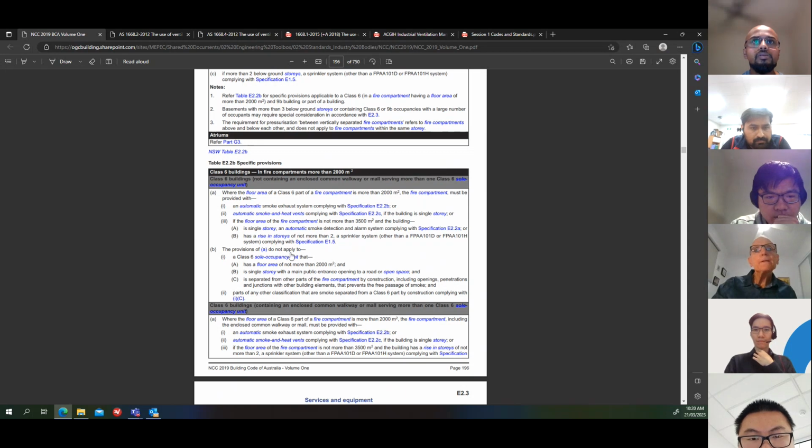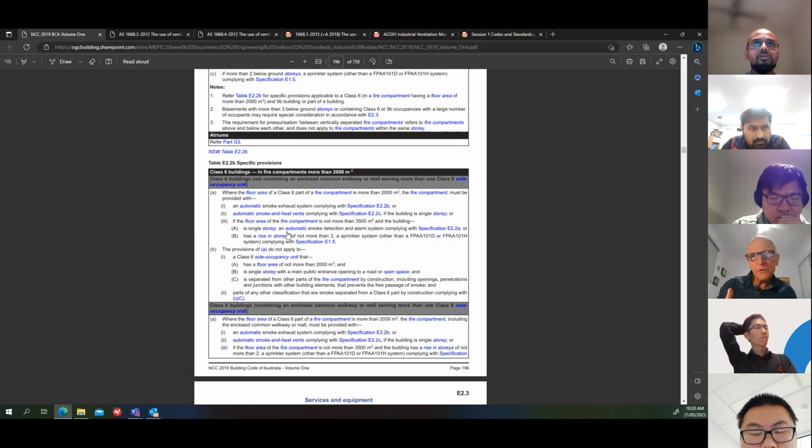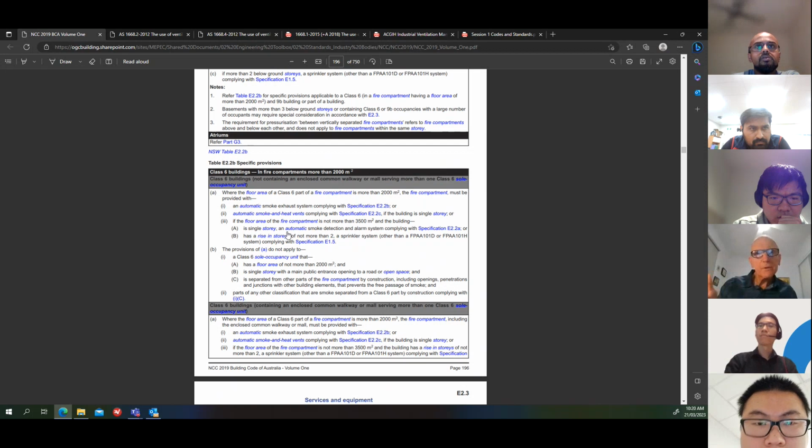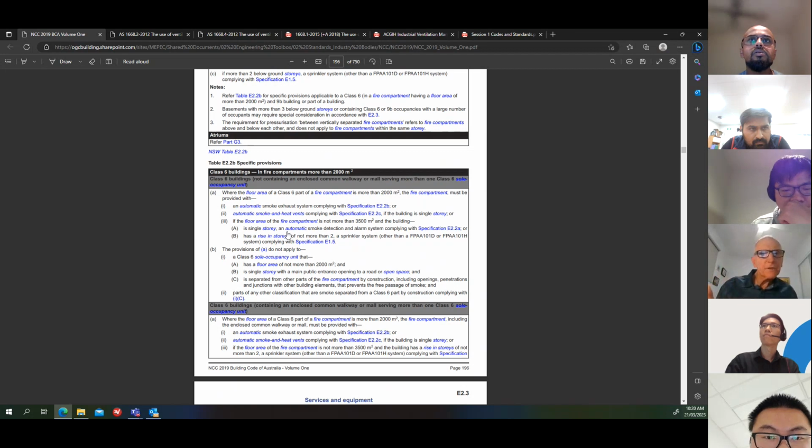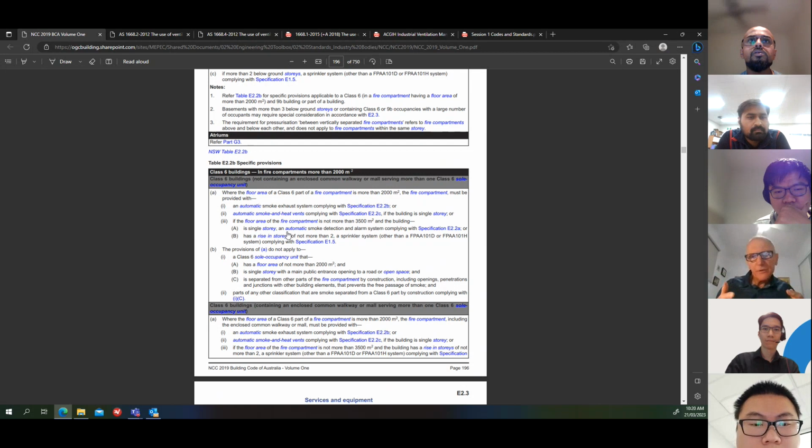And in some cases, you might be able to say to the fire protection company, if you provide a smoke detection alarm system, we may not have to provide a smoke exhaust system. Sometimes there's the option there. And it's normal that they're going to provide smoke detection alarms anyway, so you may not have to provide smoke exhaust. But the FER might say, well, for this building, you have to do it. So what I'm trying to do is give you some awareness of the interconnection between these documents and the codes as to what you need to do on a project.